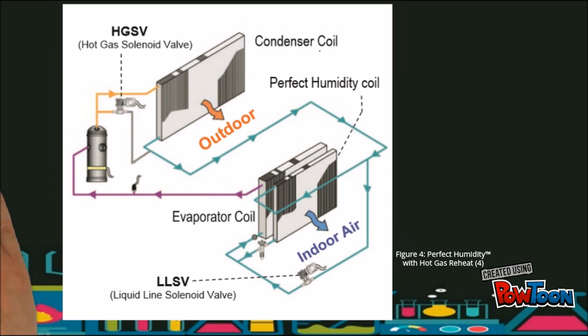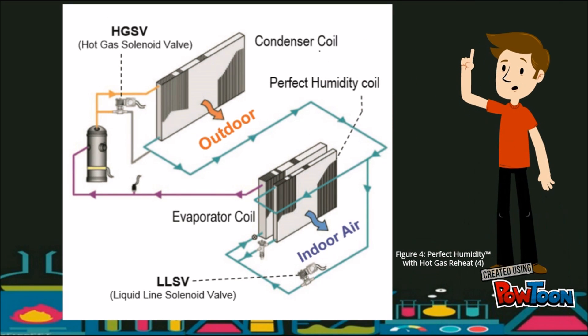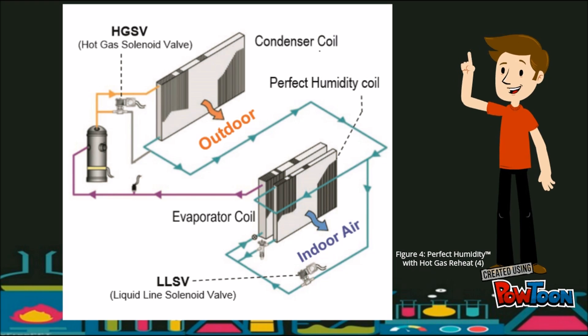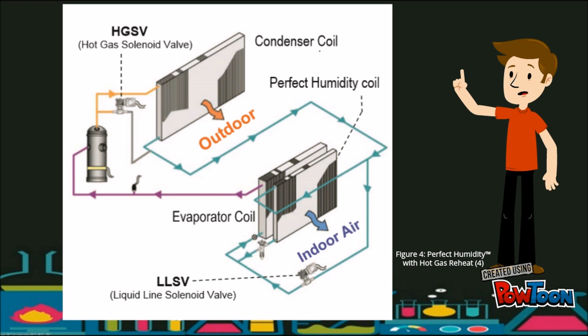When room temperature and humidity are above set point, sub-cooling mode will turn on, calling for cooling and dehumidification. In this mode, the liquid refrigerant leaves the condenser and is routed through the perfect humidity coil.